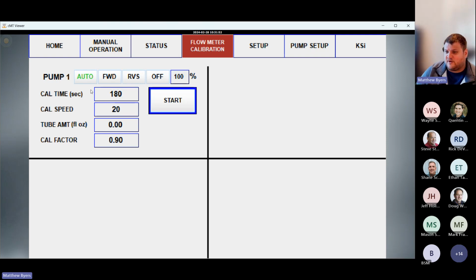We do say you should calibrate twice a day, once in the morning and once in the afternoon. You start in the morning when it's a little bit cooler and it heats up in the afternoon. That does change the viscosity a little bit, and so the cal cycle should be rerun at that point.